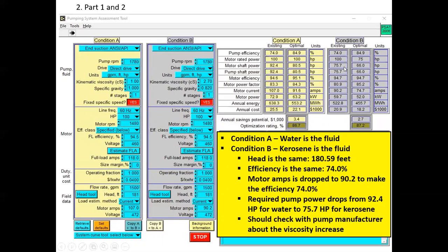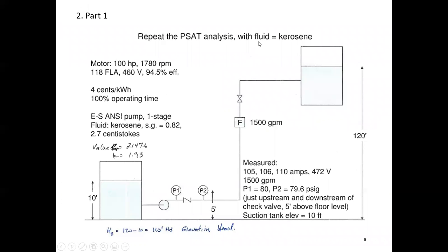Okay. So, I mean, it is interesting. If this pump is pumping 1,500 GPM of water, it's going to cost $25,500 a year. If we change it to kerosene, it's only going to cost $20,900. Kind of by the by. The optimal efficiency doesn't change on either analysis. Okay, so let's see. That's just kind of repeated the assignment.